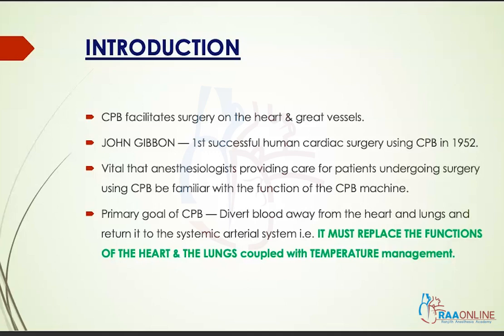The primary goal of cardiopulmonary bypass is to divert blood away from the heart and the lungs and return it to the systemic arterial system, thereby providing the surgeon with a bloodless field where he can operate comfortably and correct the lesions. In short, it replaces the function of the heart and lungs. Coupled with that, you have temperature management, which is an integral component of the cardiopulmonary bypass machine.